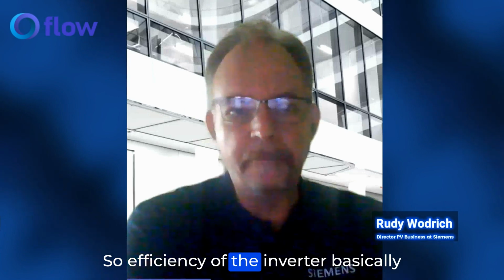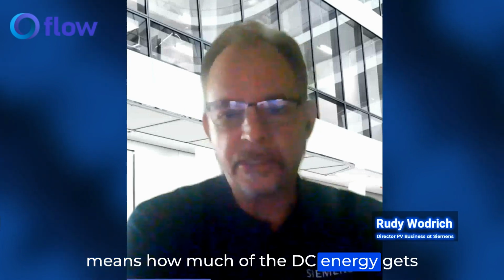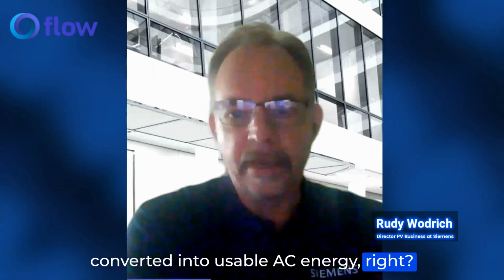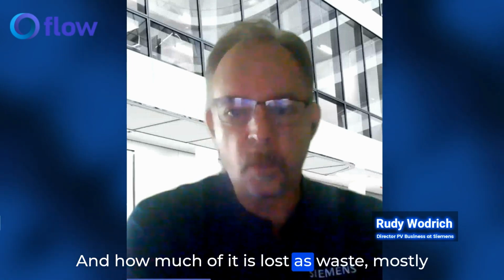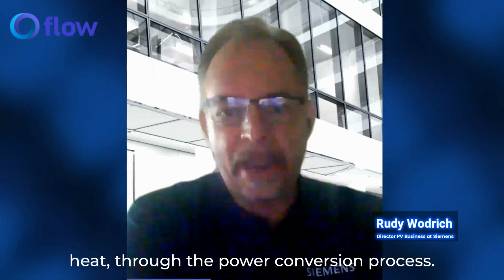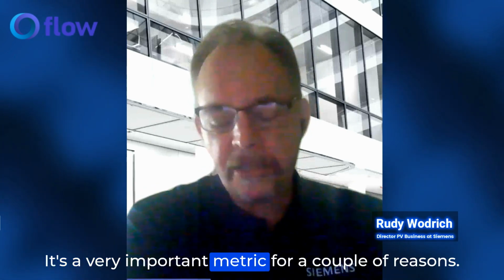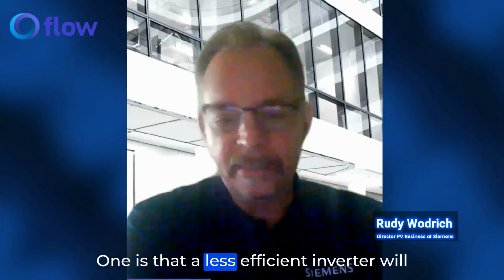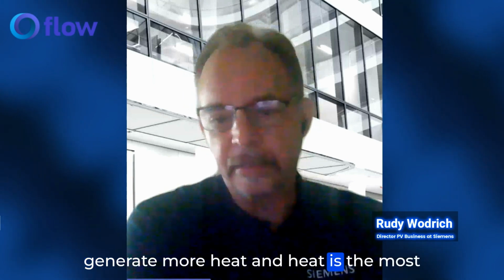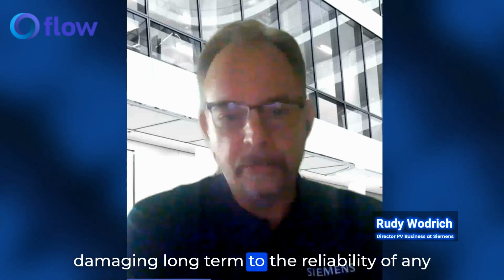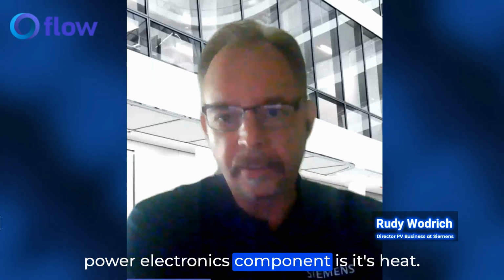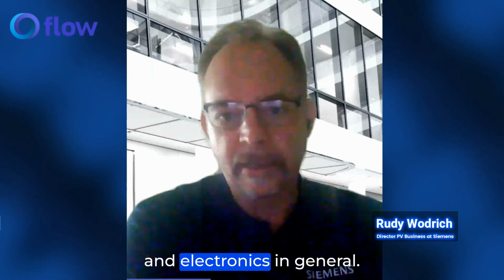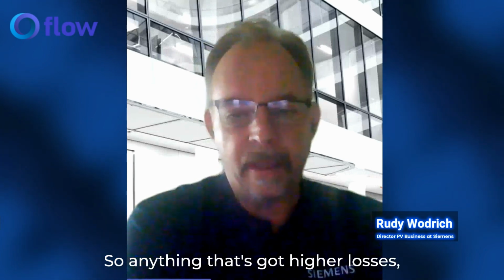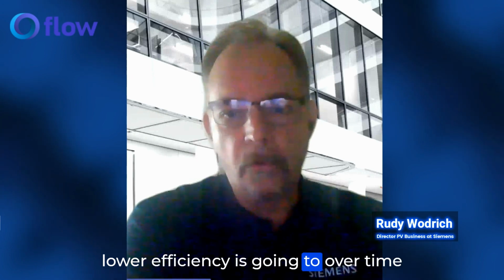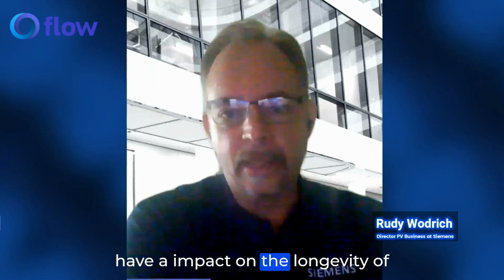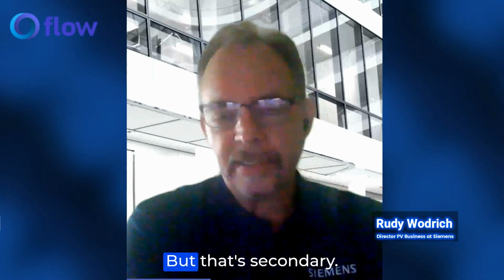Efficiency of the inverter basically means how much of the DC energy gets converted into usable AC energy, and how much is lost as waste, mostly heat, through the power conversion process. It's an important metric for a couple of reasons. One is that a less efficient inverter will generate more heat, and heat is the most damaging factor long term to the reliability of any power electronics component. That's what kills electronics in general. So anything with higher losses and lower efficiency will over time impact the longevity of the components inside the device. But that's kind of secondary.